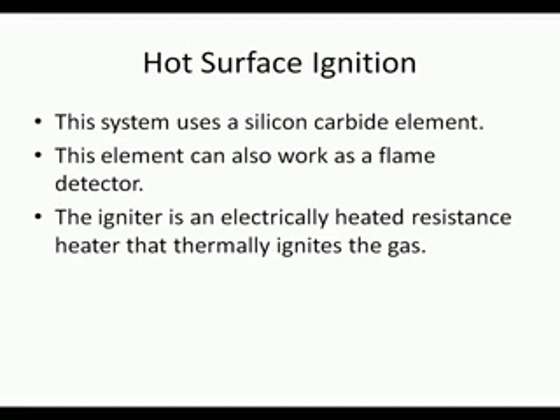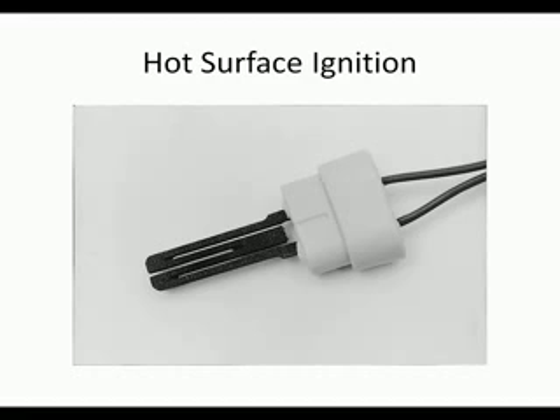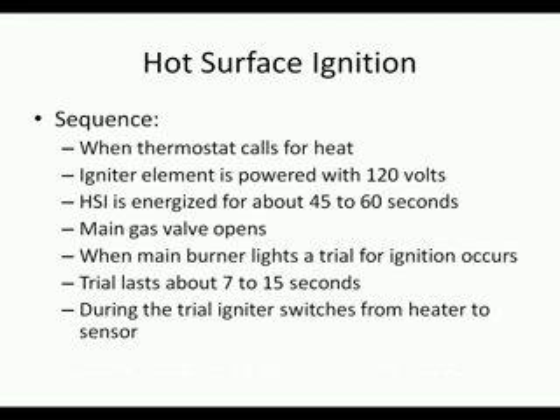The next type of ignition is the hot surface ignition. This system uses a silicon carbide element. The element can also work as a flame detector. The igniter is an electrically heated resistance heater which thermally ignites the gas. This is an example of the hot surface igniter. You have your silicon carbide tip, which is the black area, and then you have a porcelain base, which is how it is mounted.